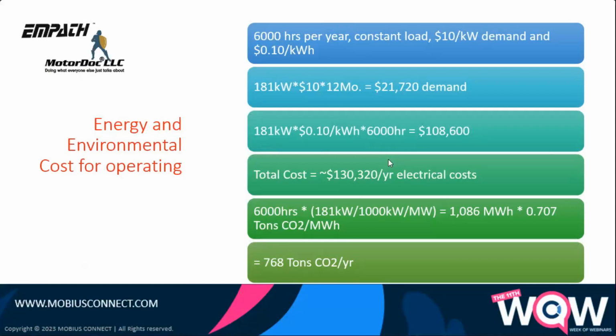So let's get back to that particular machine. From now on, I'm going to use 6,000 hours per year under a constant load at $10 per kilowatt demand and 10 cents per kilowatt hour. The reason I'm using those is because doing math while you're presenting is really bad. In any case, for that particular machine, 181 kilowatts times $10 times 12 months, if it's under the load as measured, that's $21,720 in demand. 181 kilowatts times 10 cents times 6,000, that's $108,000 for usage. The total cost is about $130,000 per year in electrical consumption just for operating the machine.